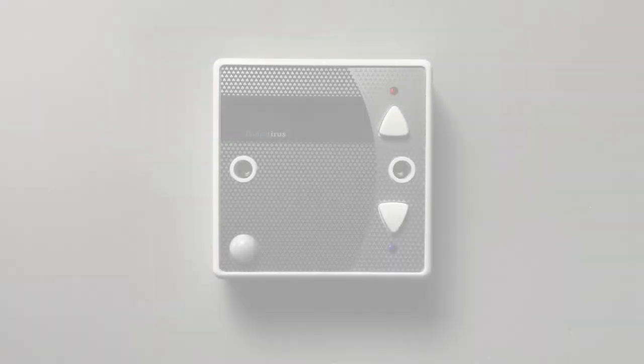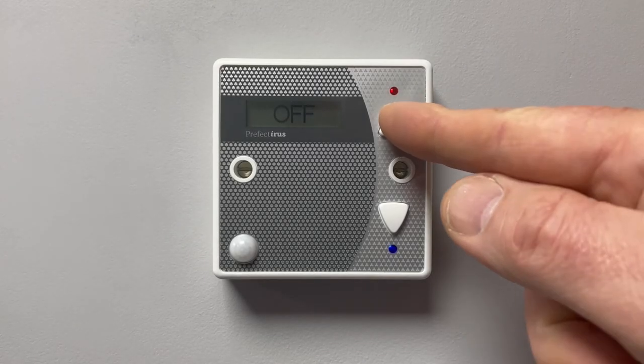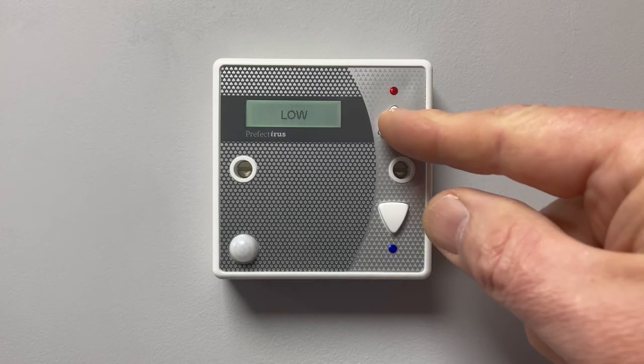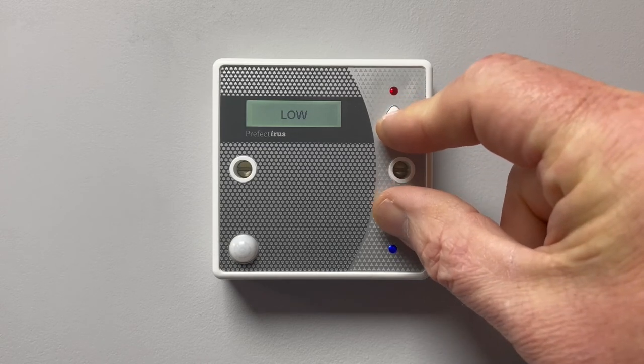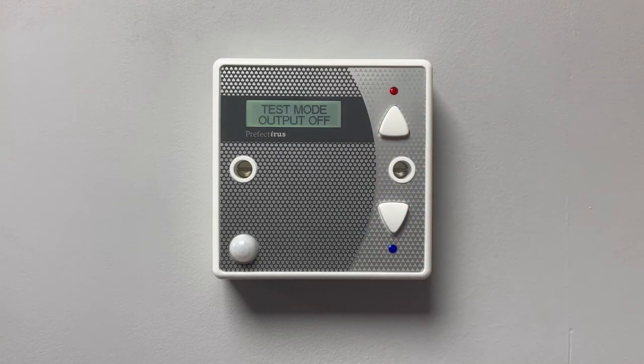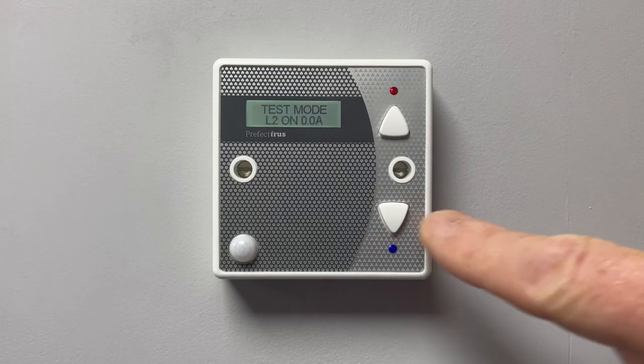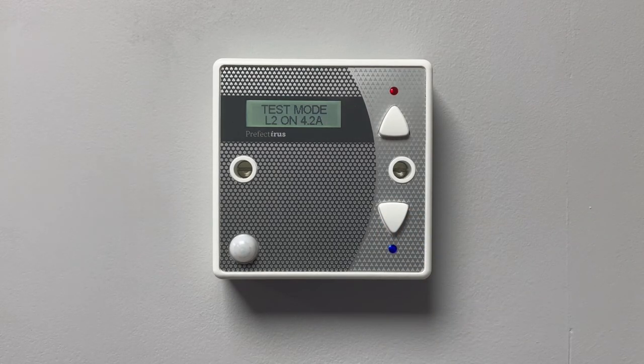Testing the heater. The heater can be tested using the control unit. Press and hold the up button and then press the down button three times in quick succession. This puts the control unit into test mode. Now press the down button one more time to enter test mode L2. This will turn the heater on. The screen will indicate amps being drawn.